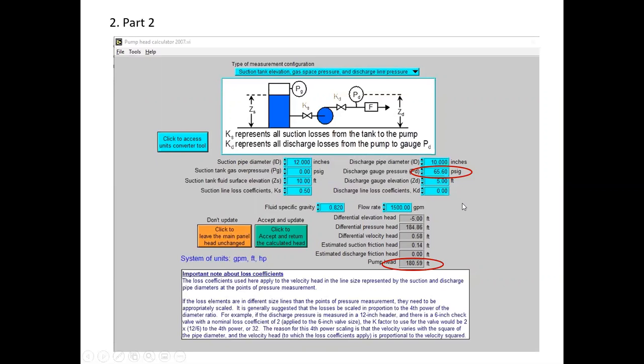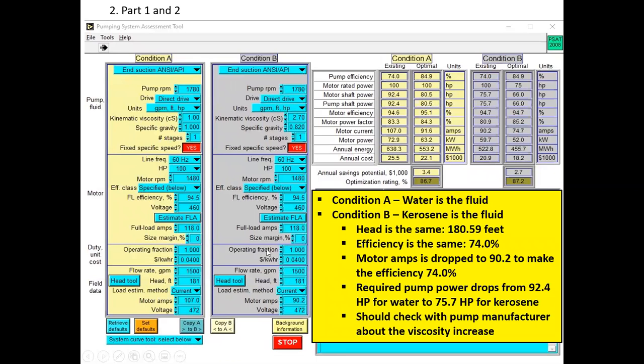Will do that for you. And so that way we maintain the same pump head. Okay, so condition A in this PSAT analysis is water, condition B is kerosene. And so I basically just hit the copy A to B button and put all the water stuff over here and then change the stuff that I needed to. So we changed the kinematic viscosity to 2.7 centistokes. We changed the specific gravity to 0.82. The rest of this didn't change.